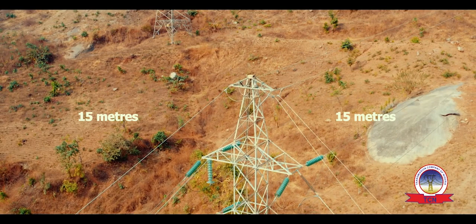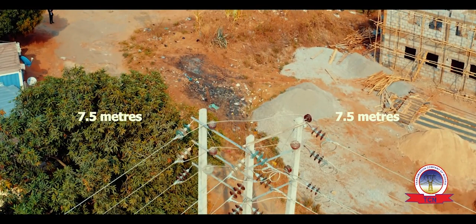Safety compliance simply means before erecting any structure around any electricity tower or line, there are safety distances you must adhere to. These safety distances are 25 meters on both sides of the tower for a 330kV line, 15 meters on both sides for a 132kV line, and 7.5 meters on both sides for a 33/11kV line. These stipulated safety distance instructions are what we call right of way.